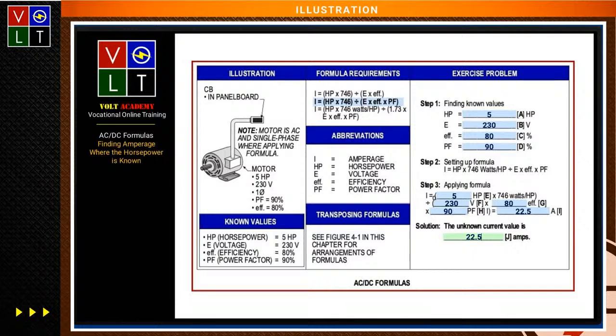Now for this one, if you look on the left-hand side under AC/DC formulas, we tell you what we're going to do: calculate and find the amperage where only the horsepower is known. So to help people understand how to perform these calculations more easily, we come in and put the known values in the illustration. We have 5 horsepower, the voltage is 230 volts, it has 80% efficiency, and the power factor is 90%.